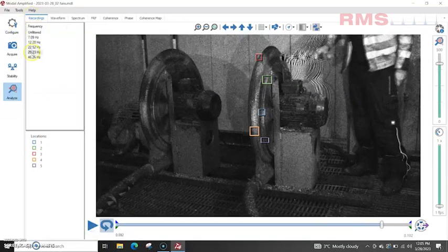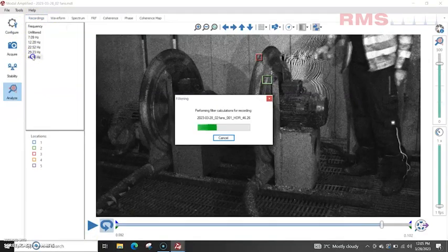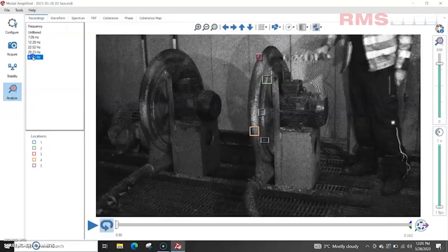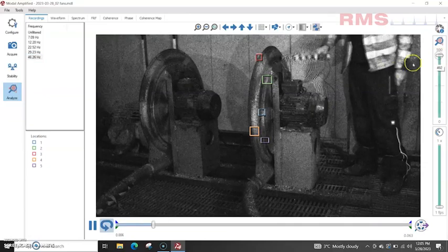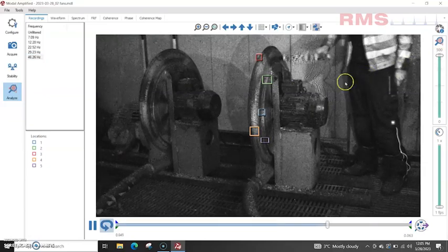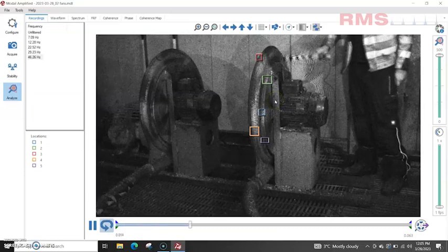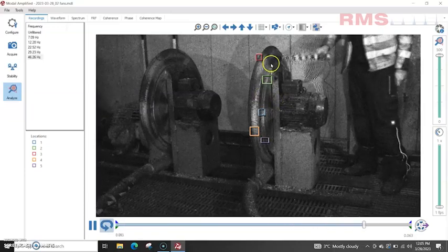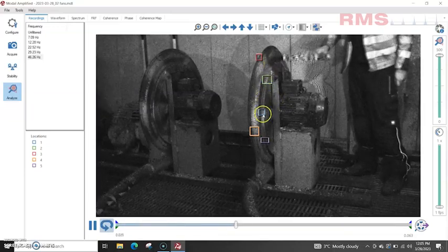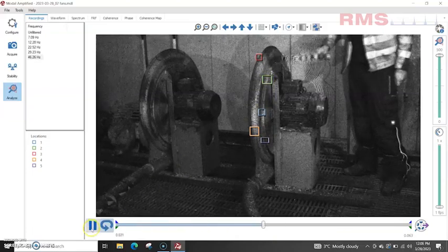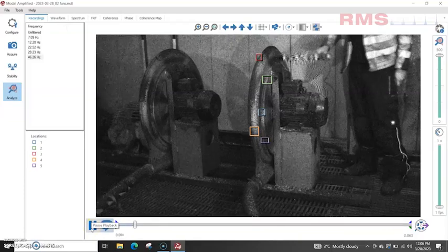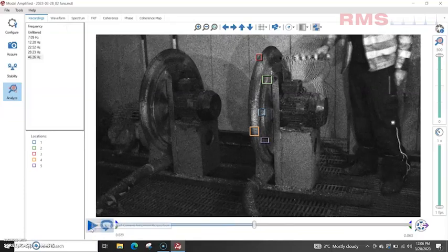Okay. And then this is an interesting one on the casing. Let's have a look. Oh yeah, I can just see. Do you know what I think I'm going to have to do here is get a bit closer, put a 25mm lens on, because it's a higher frequency. I can see sort of some separation, some rocking there on that casing. This is where we've been getting some higher vibration. Okay, that's really interesting.